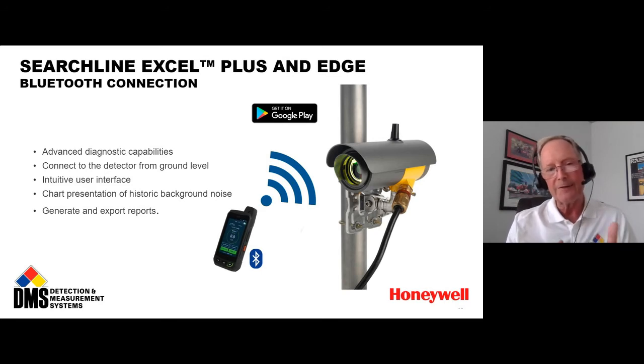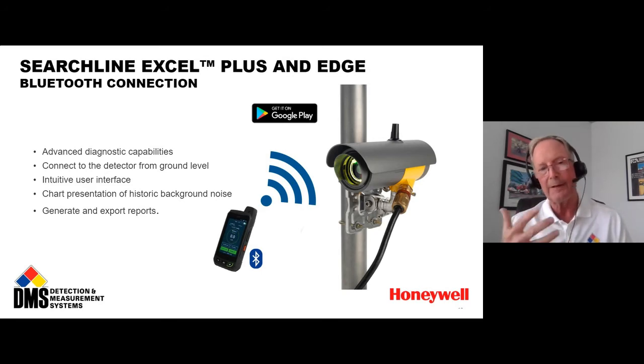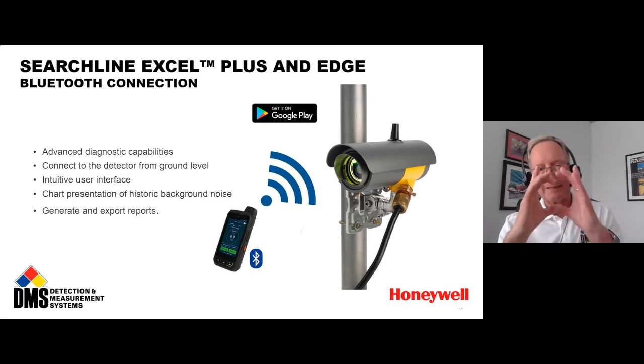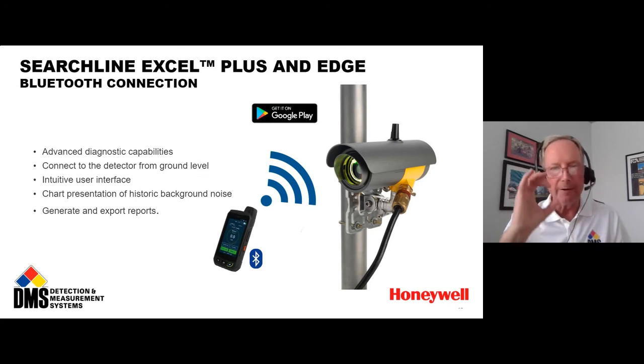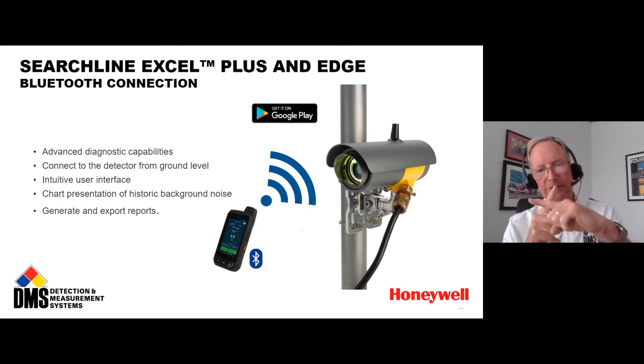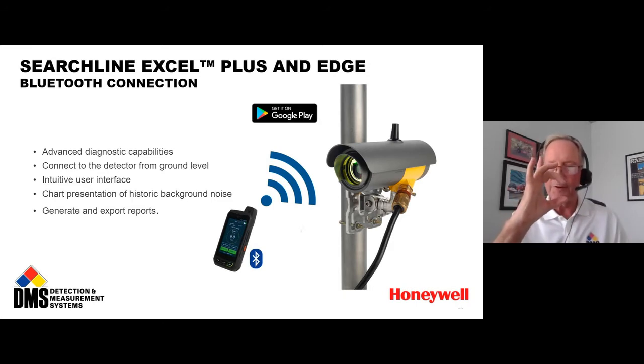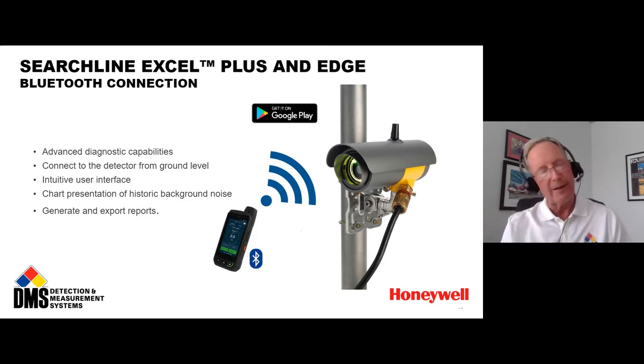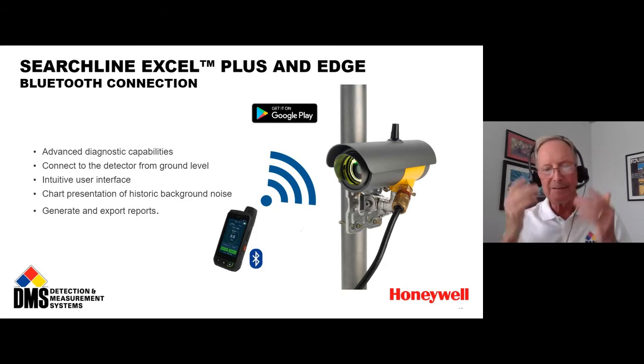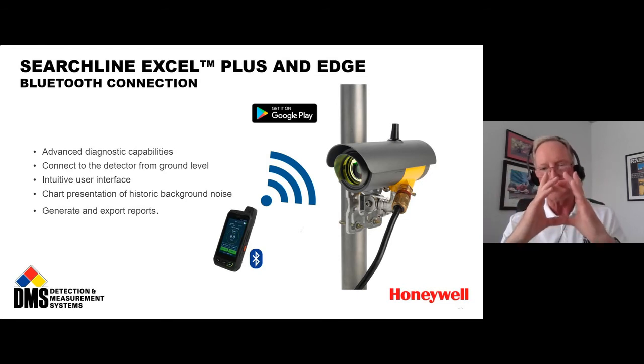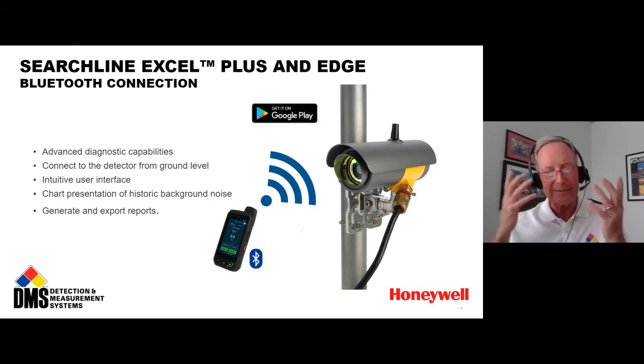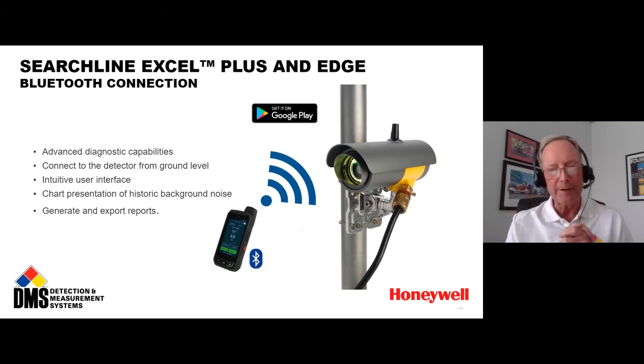What I love as well is that when shooting shorter distances, maybe 300 feet, the zoom capability gives such a clear, up-close view of the device you're aligning to at the other end—it's phenomenal. You've got crosshairs to spot the center, but they've also added 2 circles, a smaller one and a larger one, which from my experience using this provides a far better visual of exactly how it's aligned relative to the circumference of the detector. It just visually works better.